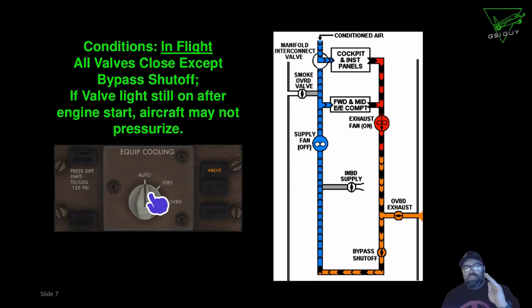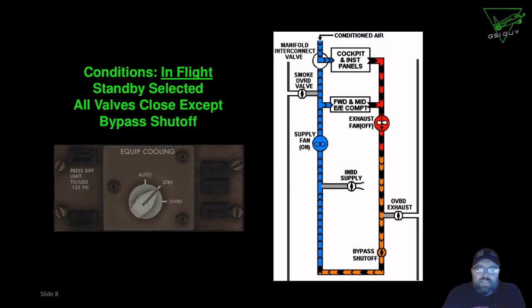And I can almost guarantee you with like 90% certainty that your QRH is going to direct you to do the same thing. You're going to run this valve light for the equipment cooling. It's going to tell you to move the switch to standby. And then the valve light will extinguish if everything moves back, because going to standby does a couple different things. So what that looks like is this. Okay, so we move to the standby position. That standby position does two things. The first thing is it's going to give a signal out to all the valves as a get right signal saying, this is the position you're supposed to be in.